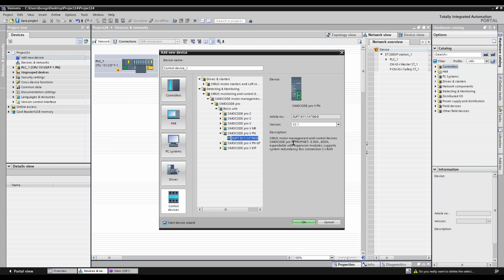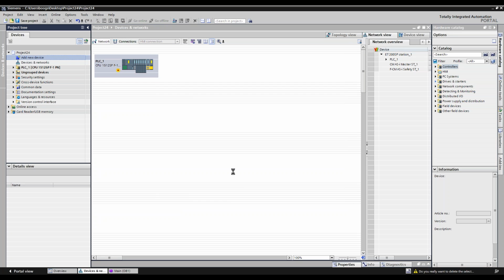Kind of gives you a description of what you selected. And if you had an older one that's been sitting on the shelf for a couple of years, you could go in and change the firmware to it, but I'm going to go with 2.1 because I've got the latest and greatest, and I'm going to hit OK. Now notice this Start Device Wizard. I highly recommend, if you haven't worked with SIMOCODE much, I still use it, even though I've worked with SIMOCODE a tremendous amount. I still like it. It's a preference. It's the way I like doing it. We're going to hit OK.